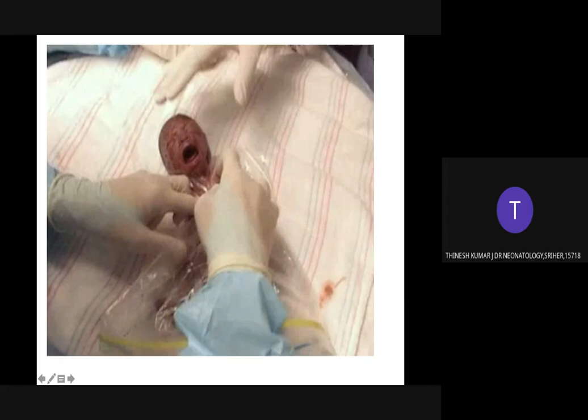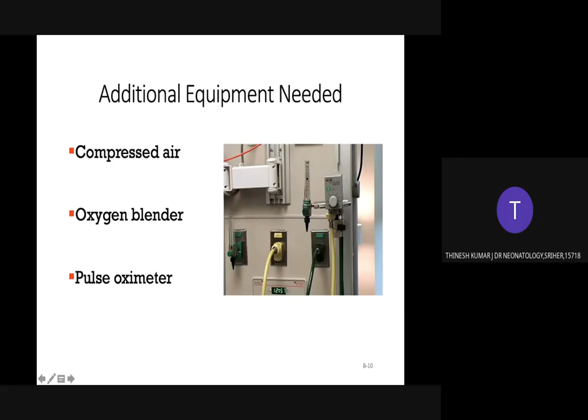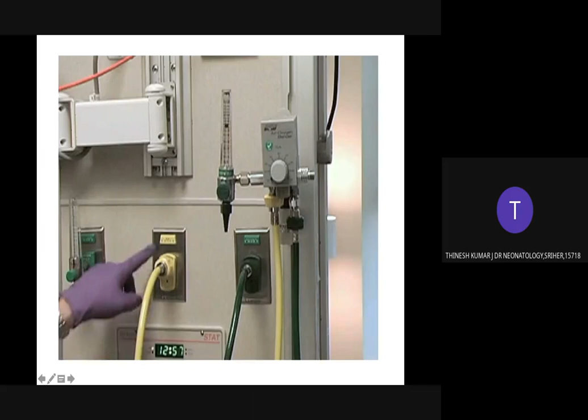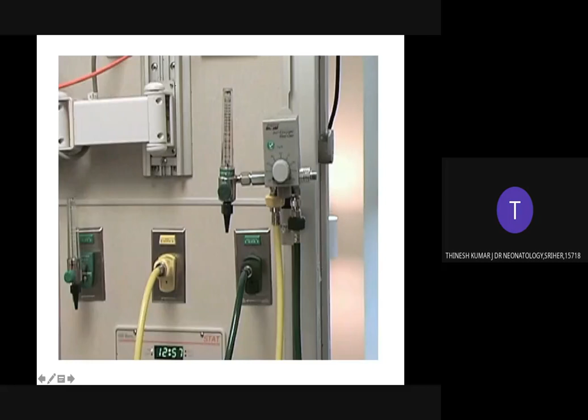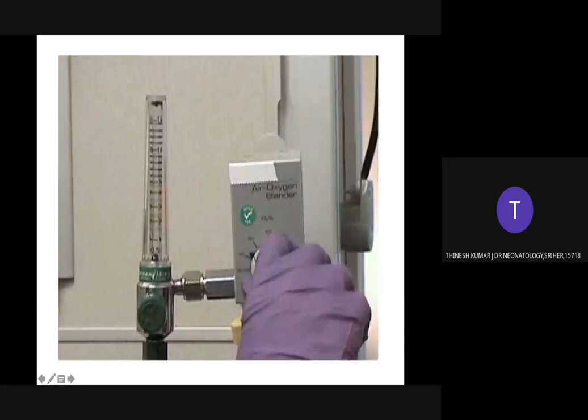The additional equipment needed are compressed air, an oxygen blender to blend air and oxygen, and a pulse oximeter to see saturation. High pressure hoses are connected from the oxygen and air sources to the blender, which has a dial that can be adjusted from 21% to 100%. An adjustable flow meter is then connected to the blender so that flows of 0 to 20 liters per minute of the desired oxygen concentration can be delivered directly to the baby or to the positive pressure delivery device.